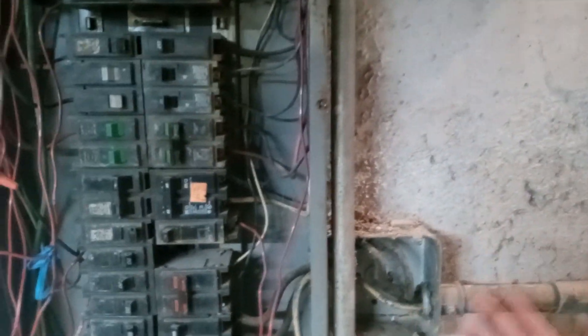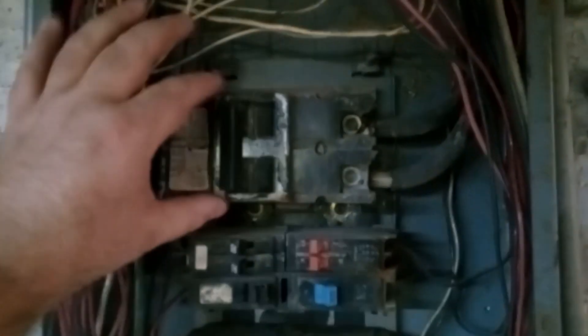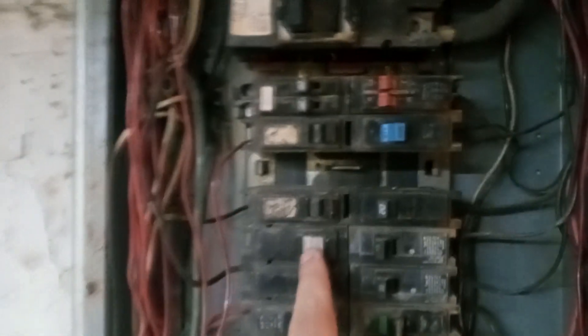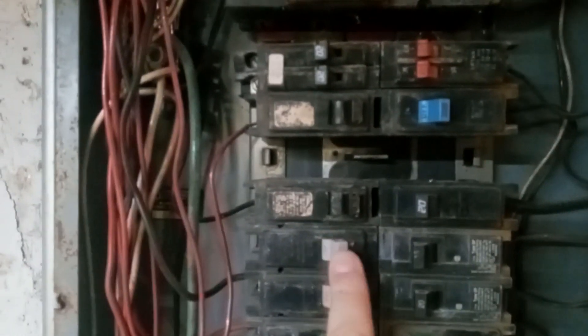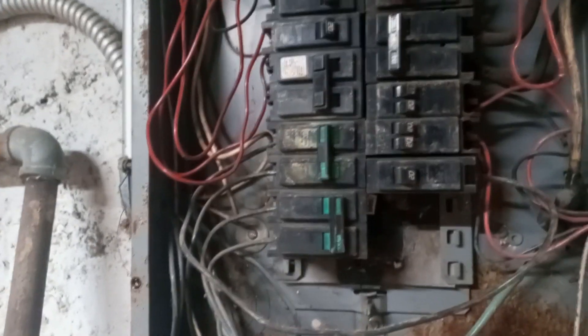It's rated up to 100 amps, and if you look, that's probably a 60 amp cable. So we're going to have to extend those, pass them through our device, splice them, come back in. We're going to switch that breaker out to a 60 — because that's a 60 amp wire. Look at that old main — scared to touch it. That's not my concern. This thing has got some breakers in here — look at that. You want to know what a broken circuit breaker looks like right there? That breaker is not resettable. It's not hooked up to anything, so it's not a problem. But it looks like we've got a 20, a 30, a 30. So we're going to have to get a 60 amp double. And then we're going to have to extend these, mount this box, and then we'll mount our rail-mountable meter in there somehow.